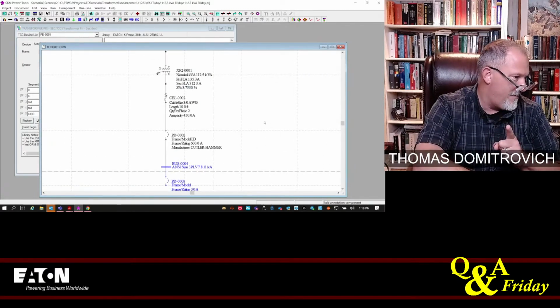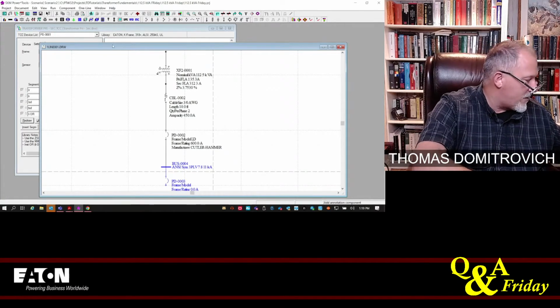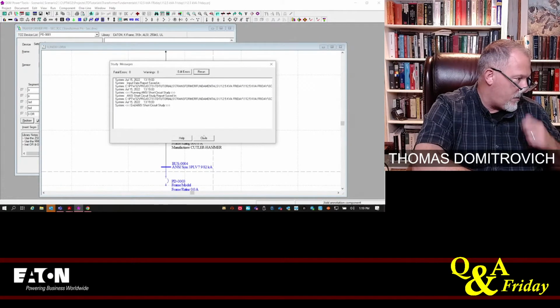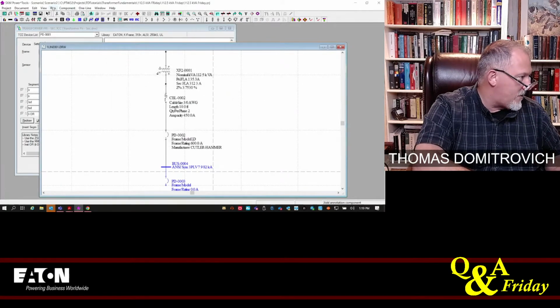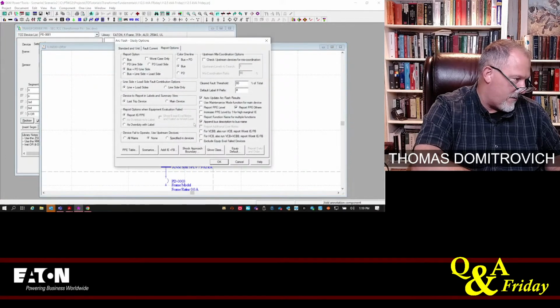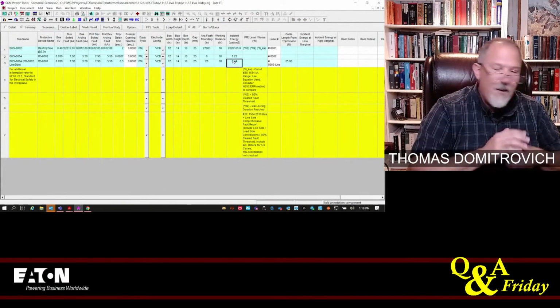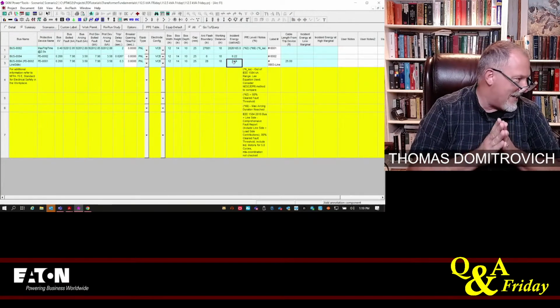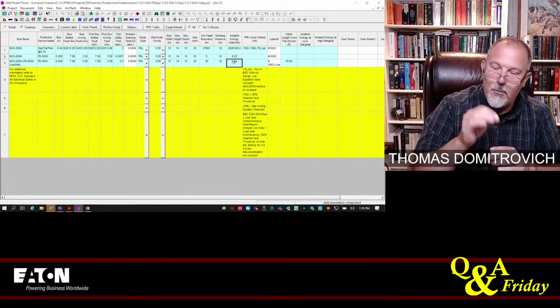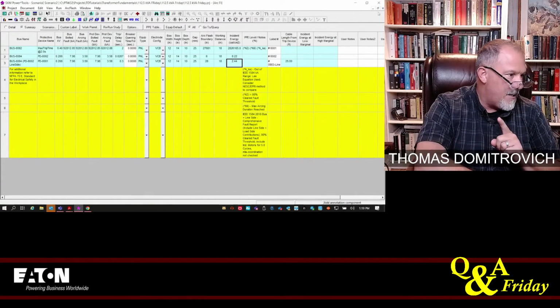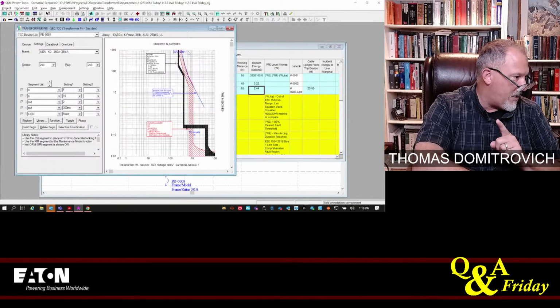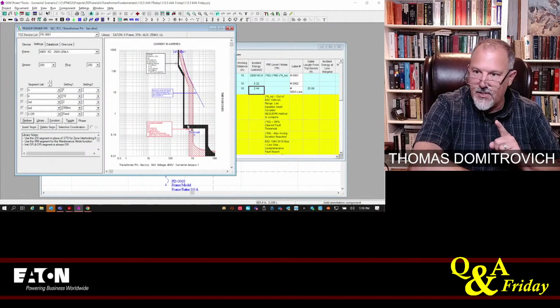Now, let's run our fault study. Control A, run. Close. Let's go back and run our arc flash evaluation. 2.44. So my incident energy now is 2.44. Why is it 2.4? Because now I'm going off of this. There you go, for on-demand availability, baby.